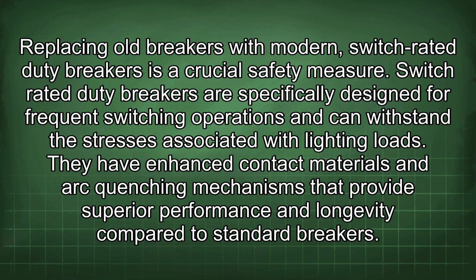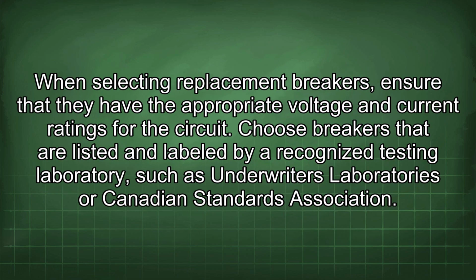Switch-rated duty breakers are specifically designed for frequent switching operations and can withstand the stresses associated with lighting loads. They have enhanced contact materials and arc quenching mechanisms that provide superior performance and longevity compared to standard breakers. When selecting replacement breakers, ensure that they have the appropriate voltage and current ratings for the circuit. Choose breakers that are listed and labeled by a recognized testing laboratory, such as Underwriters Laboratories or Canadian Standards Association.